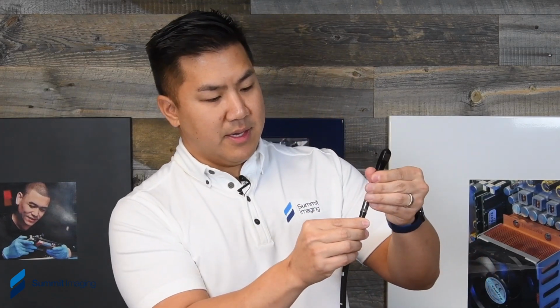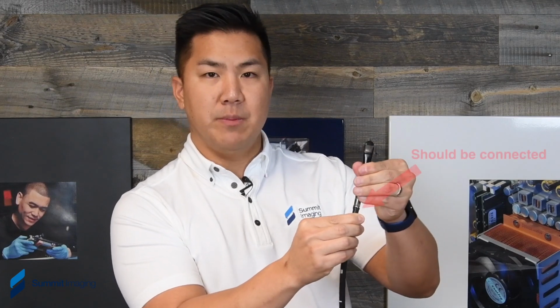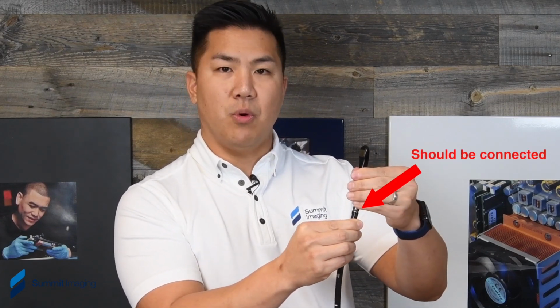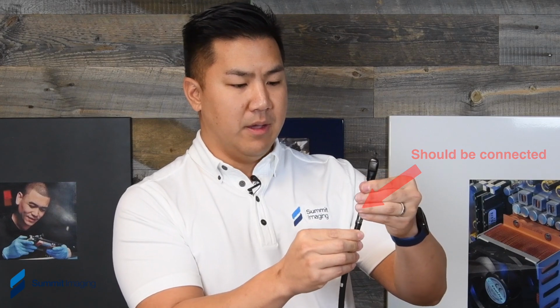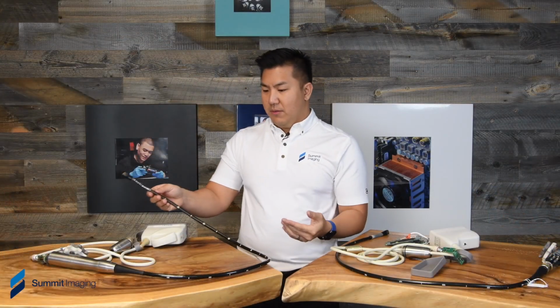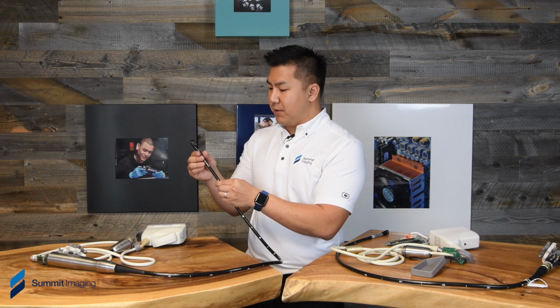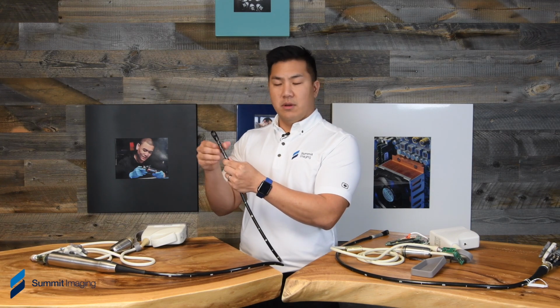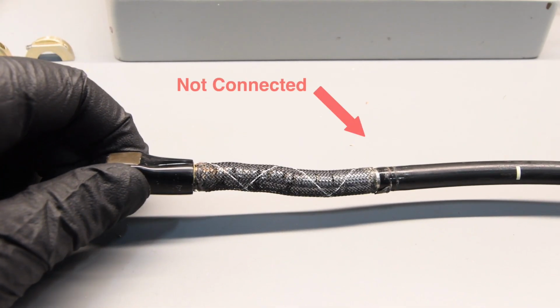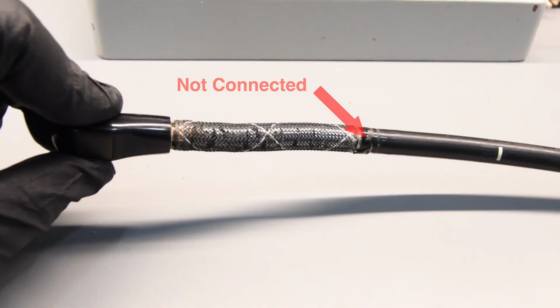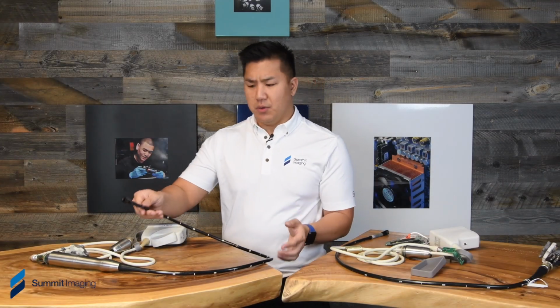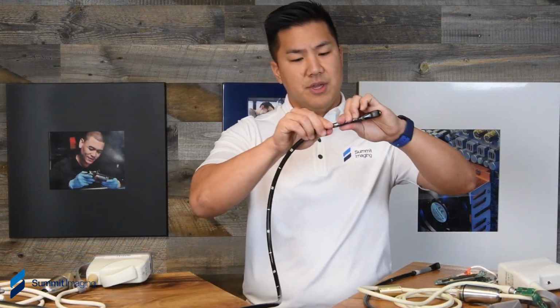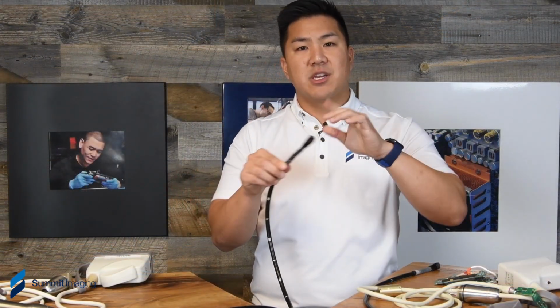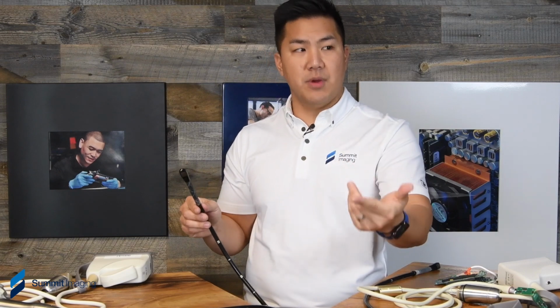And now, this was never attached, and I should not be able to spin this top portion from the insertion tube. Why is that really important? Well, for the physical properties of this part of the transducer, it's going to overstretch the bending rubber, and it's going to prematurely make the bending rubber fail because it's not designed to twist, it's designed to bend. And the other piece that's more of a clinical issue and an image quality problem is that every time this twists, that's going to cause CW noise on the screen.